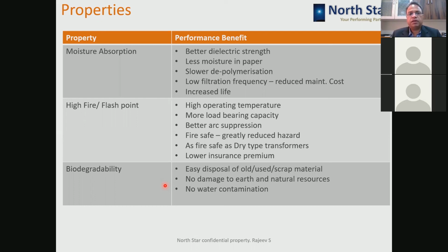Then, as they absorb high moisture, filtration frequency is very low, so your maintenance cost is lesser compared to mineral oil transformers. So with an ester-filled transformer, your maintenance cost is very low because you don't have to filter the oil. One more disadvantage of oil filtration is taking the transformer out of service, and during that period the transformer is not available, so there is loss of production. The more times you filter, the more loss there is in terms of production and revenue. And because of slow depolymerization, the life of the transformer improves. So moisture absorption brings these benefits for transformers.